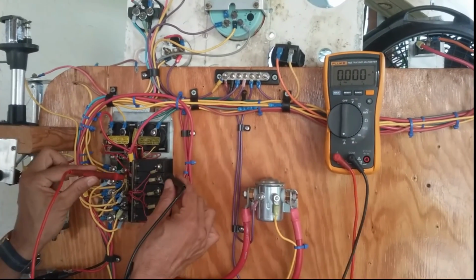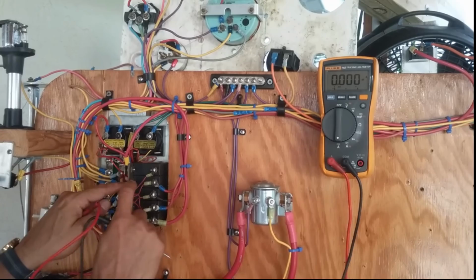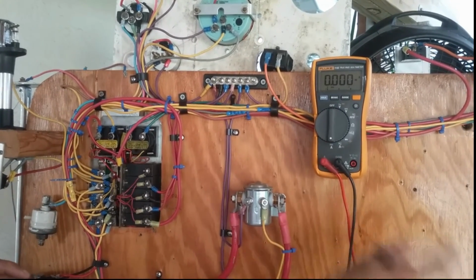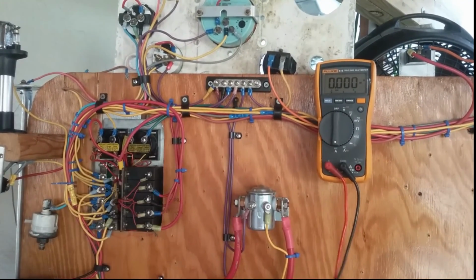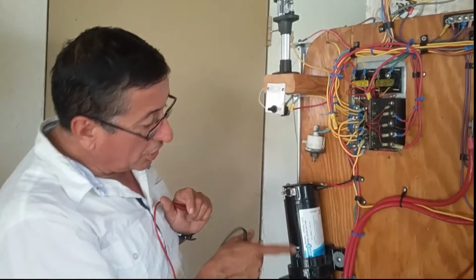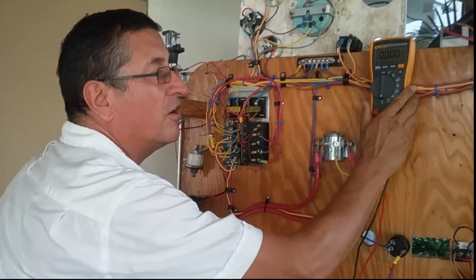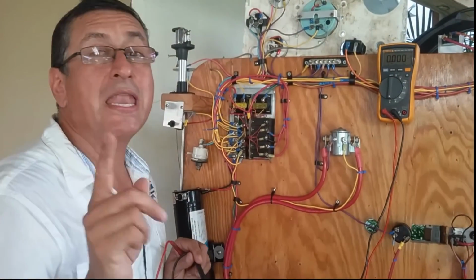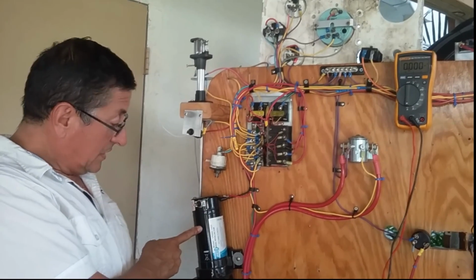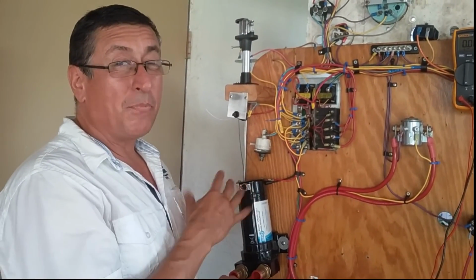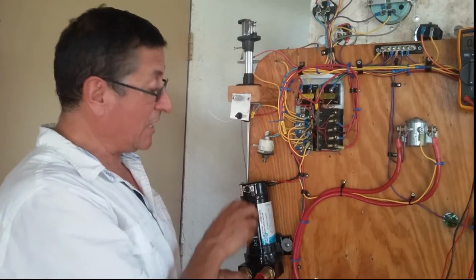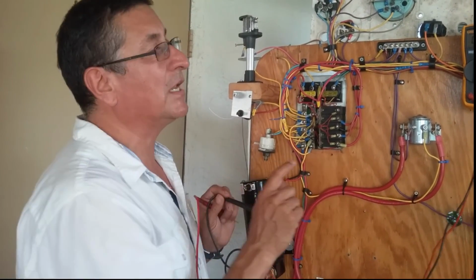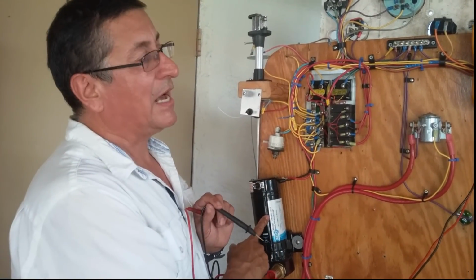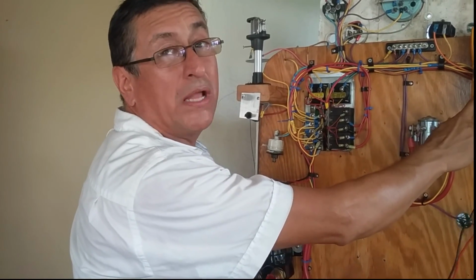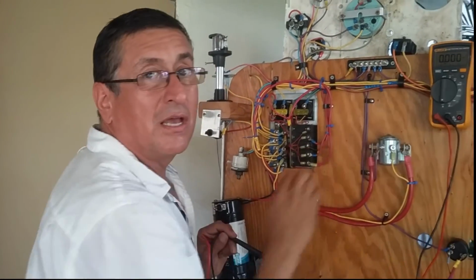Immediately I insert my ammeter, I close the gap, the fan starts, and the ammeter is reading. How much is the consumption of this pump? Remember, be careful. The capacity of the majority of the multimeters is 10 amps. I know that the consumption of this pump is 10 point something. For that reason, I am going to check the consumption of this and I disconnect quickly because it's more than 10. I don't want to damage and I don't want to blow the fuse of this multimeter.